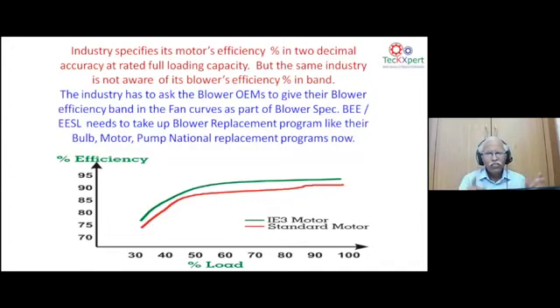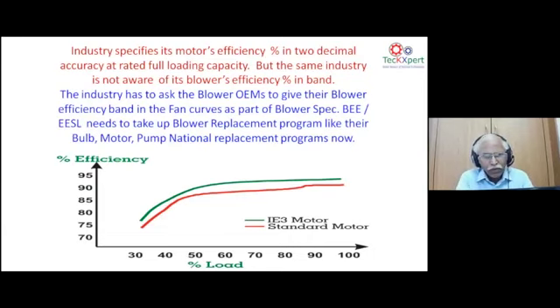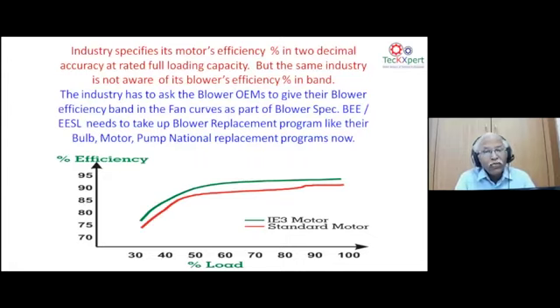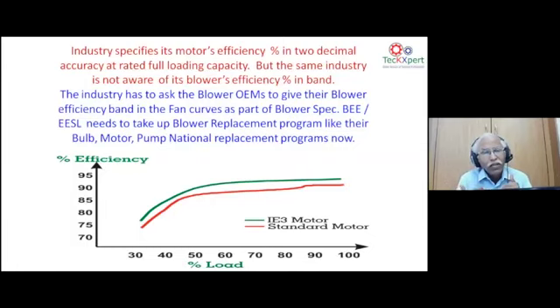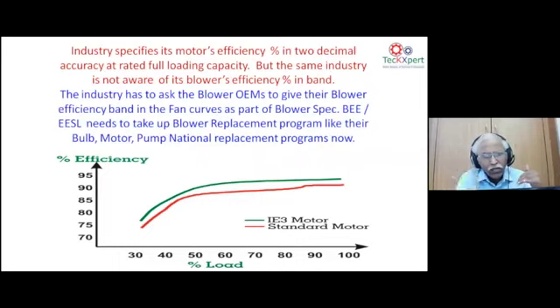Industries specify motor efficiency to two decimal places — 92.3%, 92.35% — and it's a flat efficiency curve from 55–95% load. But the same industries, whether large or MSME, are largely unaware of their blower's efficiency band. They don't know or haven't been informed of the blower's operating efficiency. The blower has a narrow efficiency band, and whether the blower and motor efficiencies are collectively matched for best combined performance is often not checked.